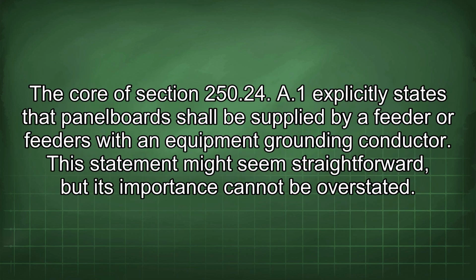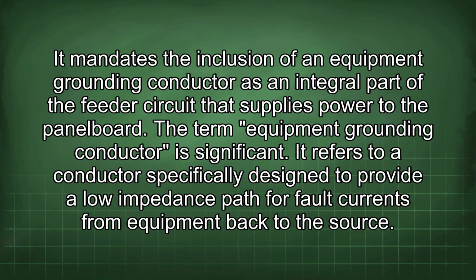The core of Section 250.24(a)(1) explicitly states that panelboards shall be supplied by a feeder or feeders with an equipment grounding conductor. This statement might seem straightforward, but its importance cannot be overstated. It mandates the inclusion of an equipment grounding conductor as an integral part of the feeder circuit that supplies power to the panelboard. The term equipment grounding conductor is significant.